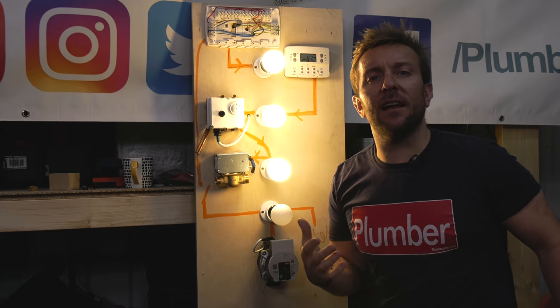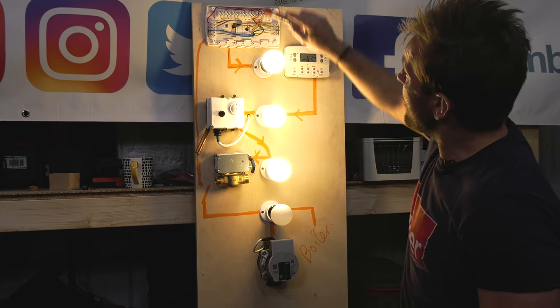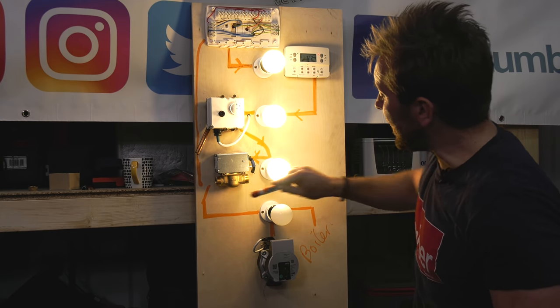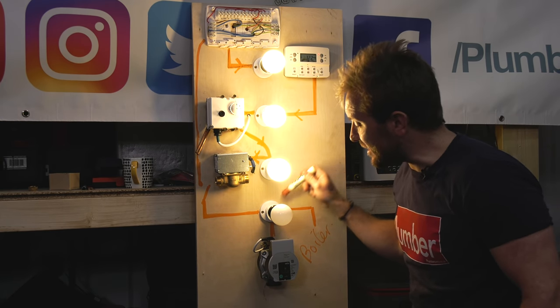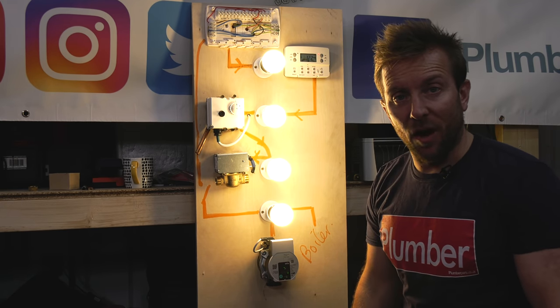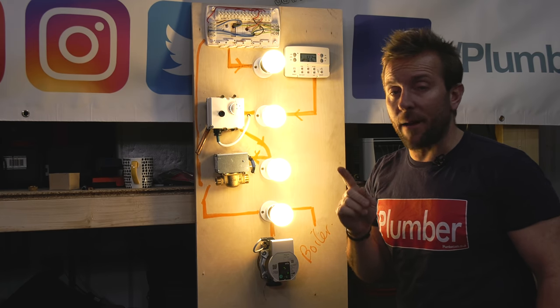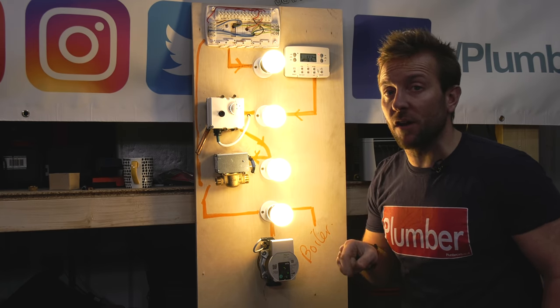Okay. Oh, suddenly we've used some water. The tank's getting cold. We're sending a live to that. The permanent live in the switch here is waiting, waiting, waiting. And then bang, there we go. Live supply. That's how these systems are wired up. You only have to worry about one live. It goes off in little different directions.